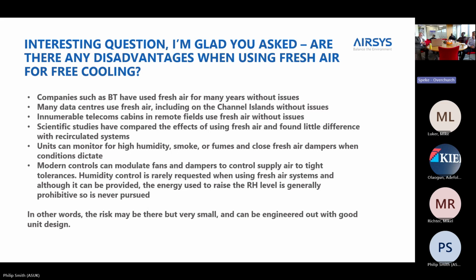The only issue with fresh air is that you are restricted in controlling your humidity levels within the space. And to add to that, most server technologies these days aren't really worried as long as it's between 20 and 80% RH and isn't fluctuating too quickly. So when you're bringing in fresh air in the winter, because it's cold, you bring less fresh air in, so you're not introducing as much low humidity air. So is it a problem? No. In reality, you could humidify if you wanted to, but that then negates any of the energy savings you're getting by running fresh air.